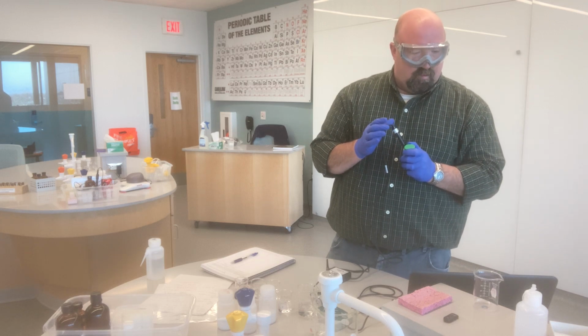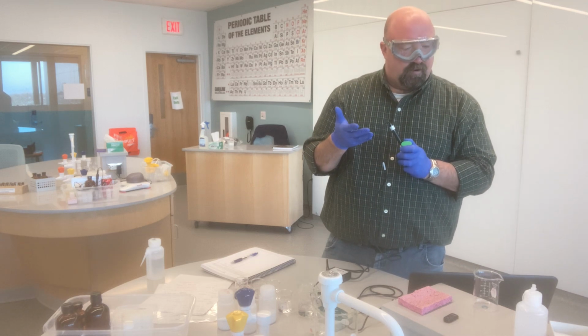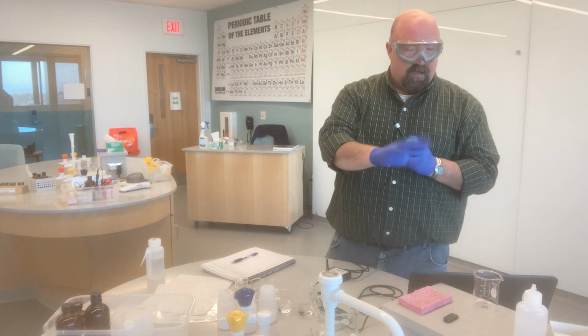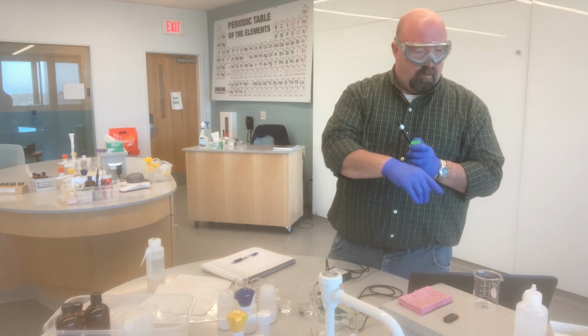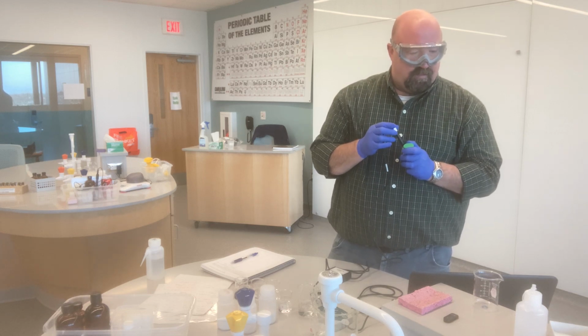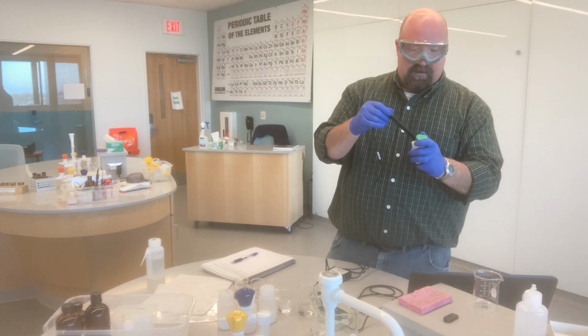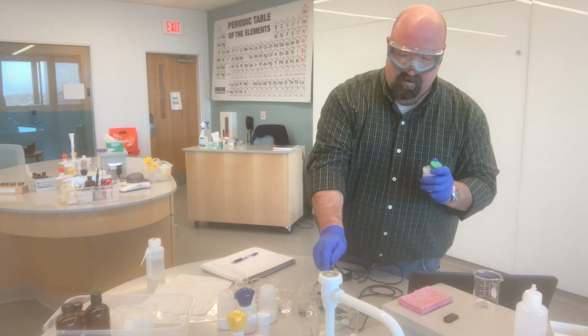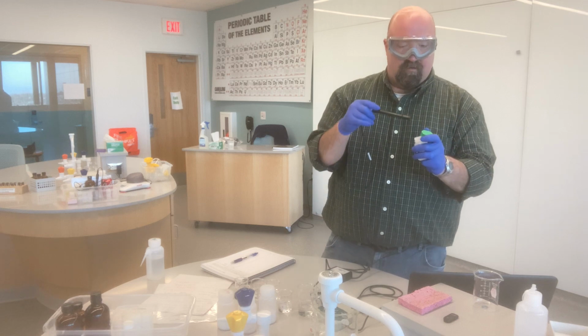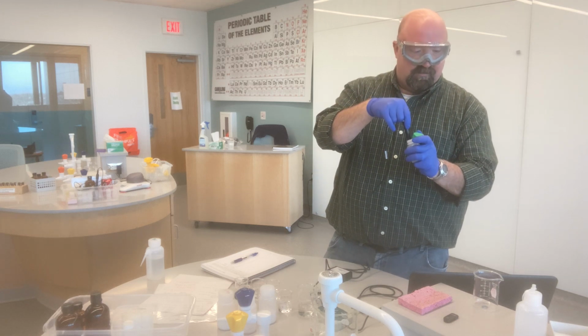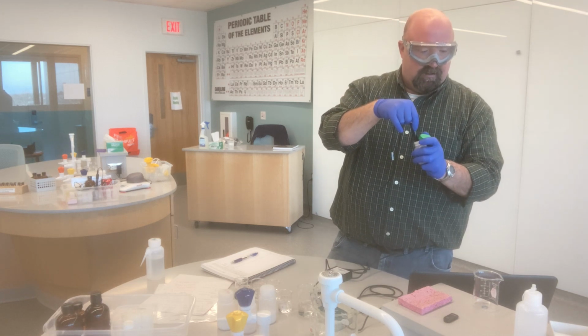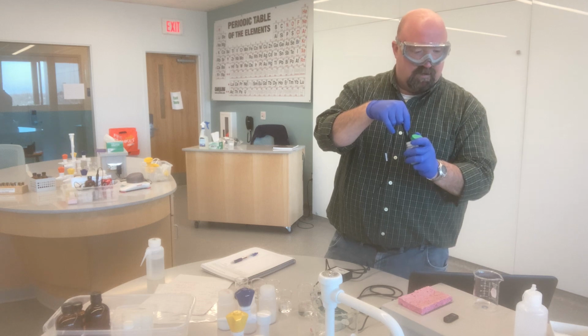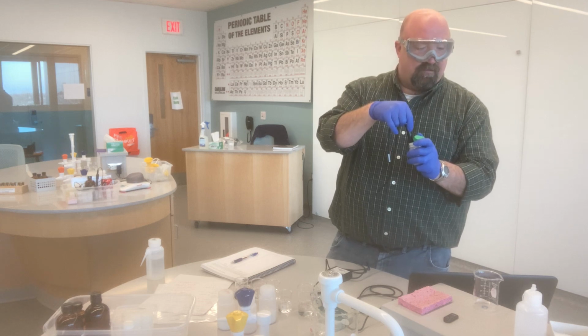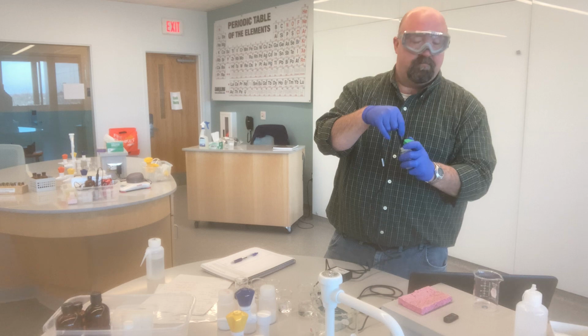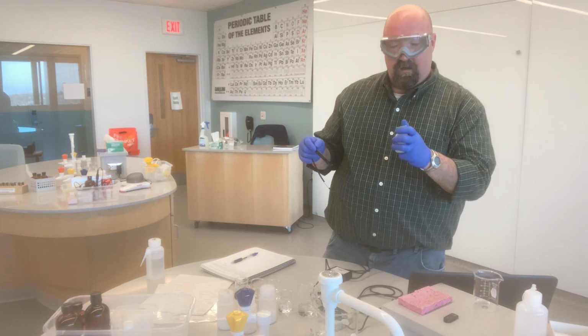And just as you saw what the screen looked like with the turbidity video, what I'm looking at here is just that Logger Pro screen, which is measuring my conductivity down in the lower left. To double check that it is measuring the standard correctly, I'm just going to take it out, stick it back into the standard, and I see that it is measuring the standard at 1003 microsiemens per centimeter. So that tells us that we're pretty well calibrated.